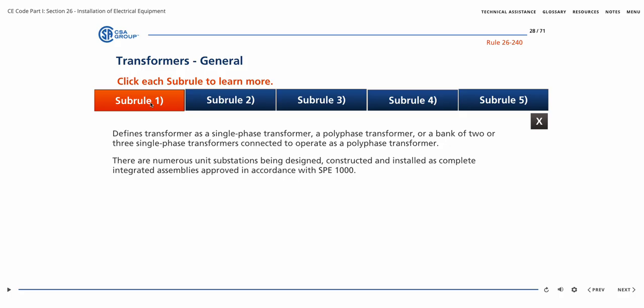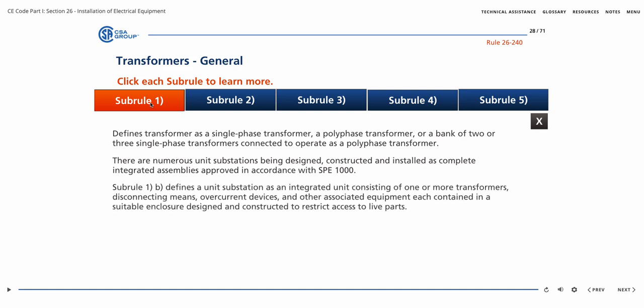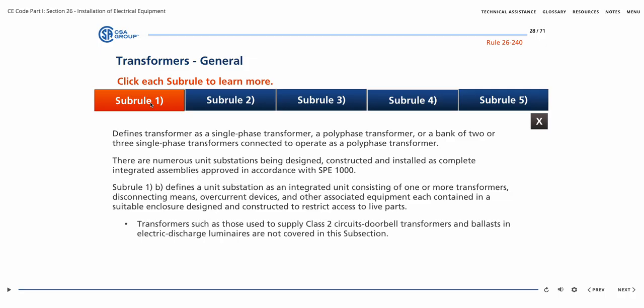There are numerous unit substations being designed, constructed, and installed as complete integrated assemblies approved in accordance with SPE 1000. Subrule 1B defines a unit substation as an integrated unit consisting of one or more transformers, disconnecting means, overcurrent devices, and other associated equipment, each contained in a suitable enclosure designed and constructed to restrict access to live parts. Transformers such as those used in Class II circuits, doorbell transformers, and ballasts in electric discharge luminaires are not covered in this subsection.